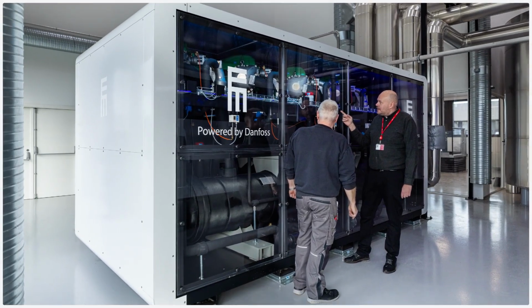By tying the two energy systems in together, the hospital has achieved a significant energy efficiency increase and operating cost reduction. This included a COP during the winter periods, the most challenging operation, of 2.8 on the cooling side and 3.8 on the heating side, or roughly 4 times the gas boiler efficiency that it was replacing.